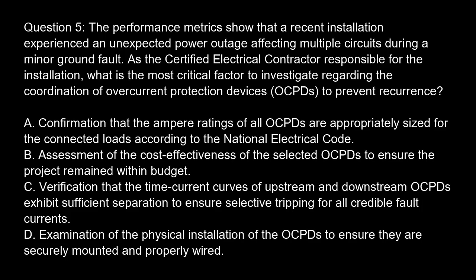Question 5. The performance metrics show that a recent installation experienced an unexpected power outage affecting multiple circuits during a minor ground fault. As the certified electrical contractor responsible for the installation, what is the most critical factor to investigate regarding the coordination of overcurrent protection devices, OCPDs, to prevent recurrence? Option A. Confirmation that the ampere ratings of all OCPDs are appropriately sized for the connected loads according to the National Electrical Code. Option B.